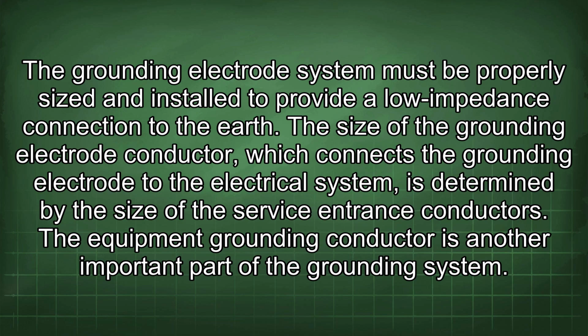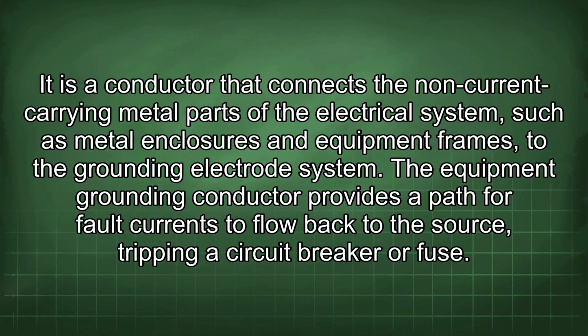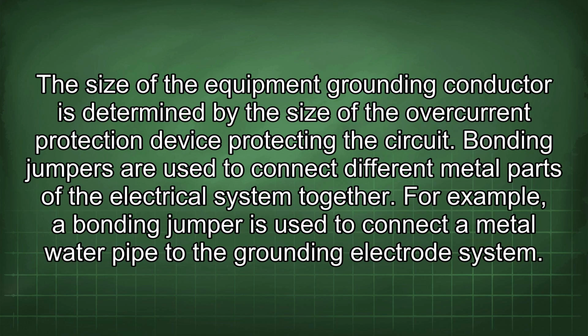The equipment grounding conductor is another important part of the grounding system. It is a conductor that connects the non-current carrying metal parts of the electrical system, such as metal enclosures and equipment frames, to the grounding electrode system. The equipment grounding conductor provides a path for fault currents to flow back to the source, tripping a circuit breaker or fuse. The size of the equipment grounding conductor is determined by the size of the overcurrent protection device protecting the circuit.